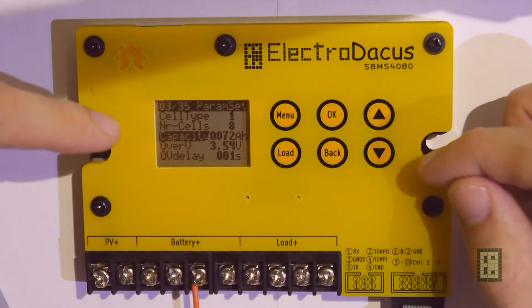Then you have this saved, and when you enter here you see the values that you have stored in the EEPROM when you first enter the parameter setting. So you see it's not the default 100 amp hour, it's 72 amp hour, and the over voltage is 3.54, not 3.55 like the default.